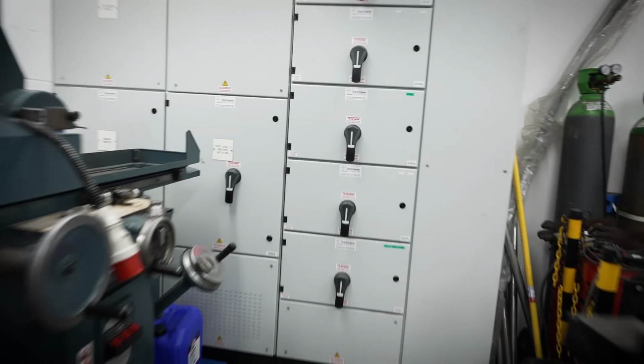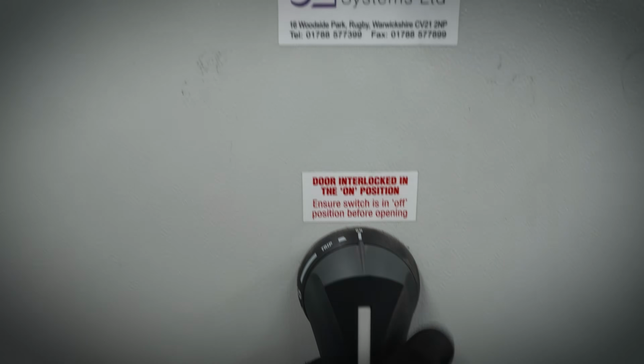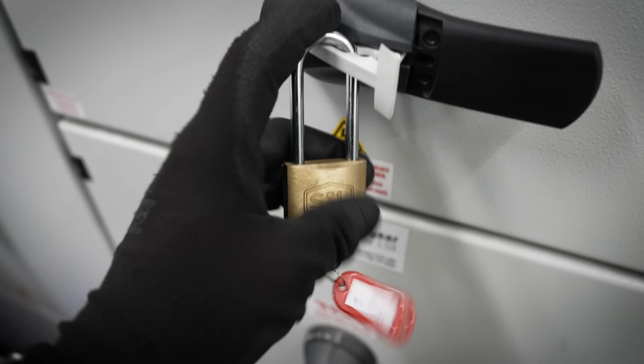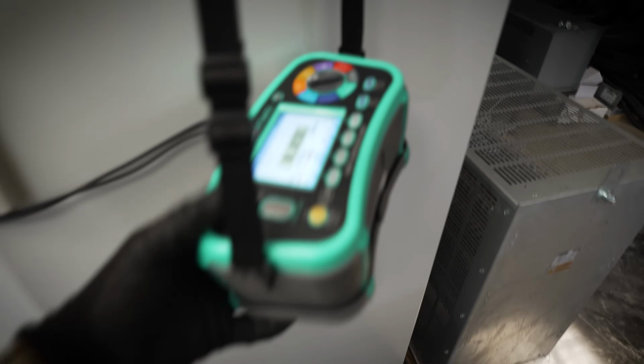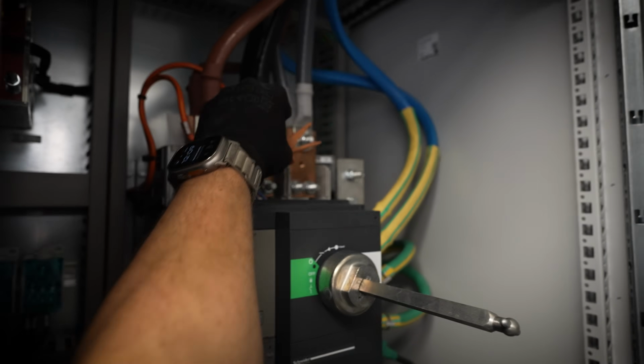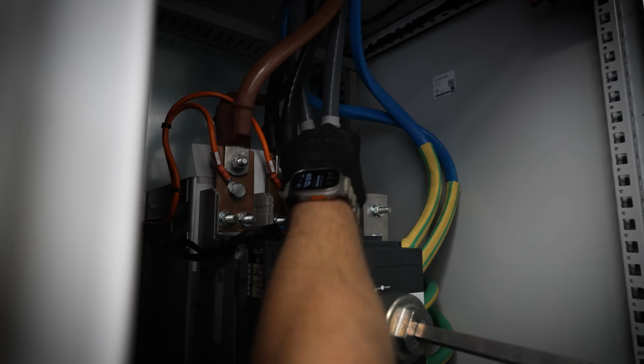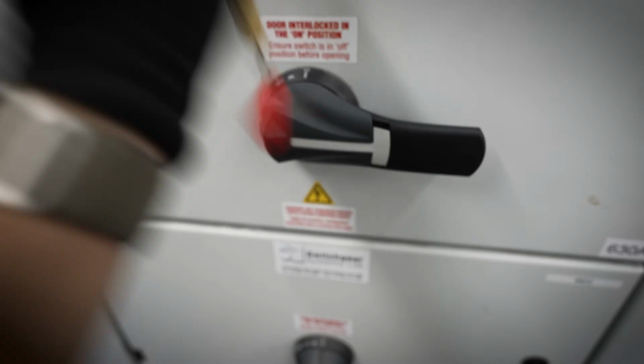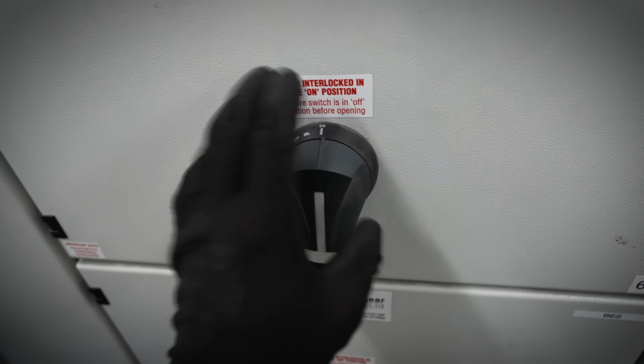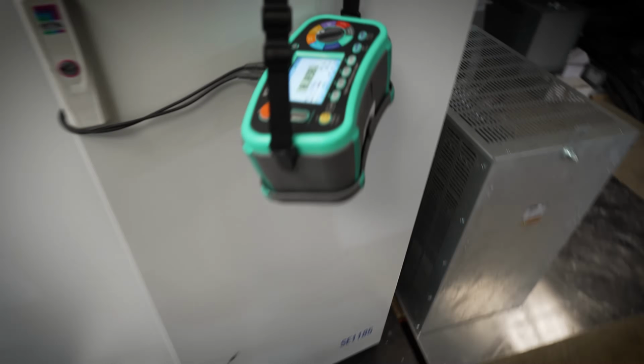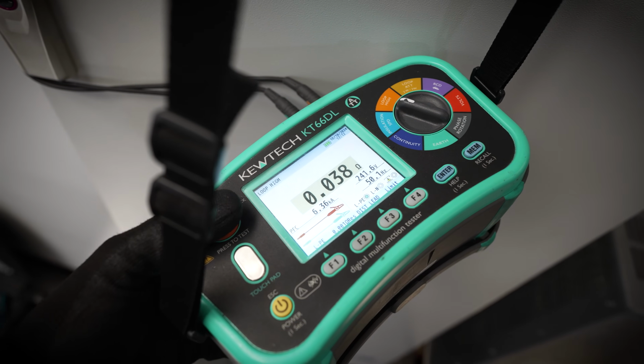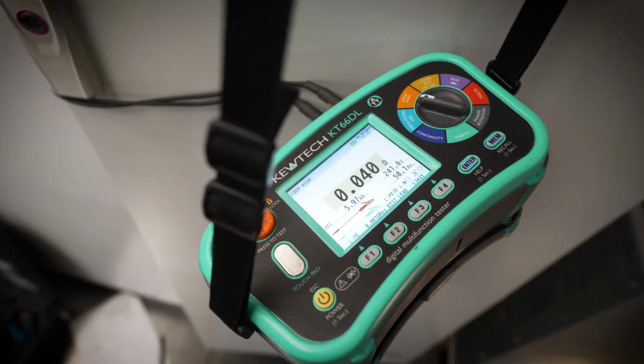0.38. Again, I'm gonna turn it off, lock it off. Let's double check. Yeah, we got no voltage. Get you onto L3. Move the isolation. Turn it on again. What have we got? 230, so let's press test. 0.40. Right, that's our live tests complete on this one.